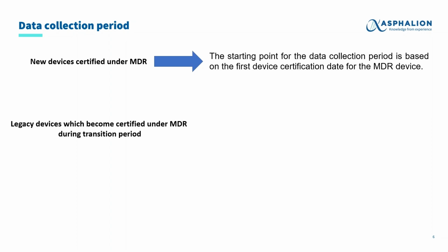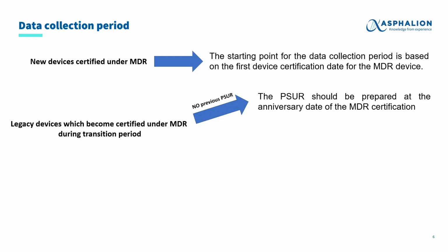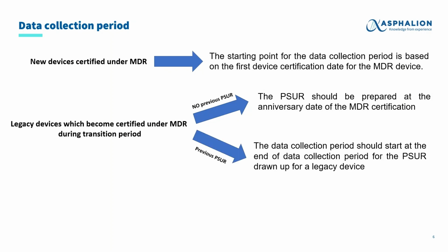On the other hand, for those legacy devices that are on the market under MDD certification, but that will become MDR during the transition period, we have two possibilities. If no previous PSUR has been prepared, the starting point for the data collection period will be the certification date of the MDR. However, if a previous PSUR has been issued, the data collection period should start at the end of the data collection period of the previous PSUR, so that there is no period of time left between PSURs.